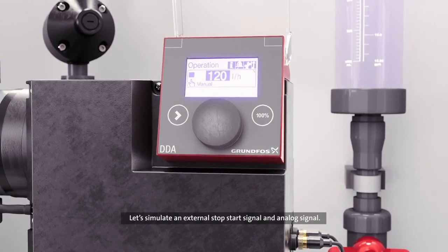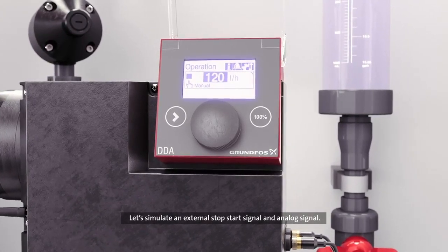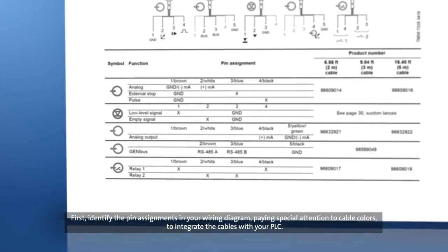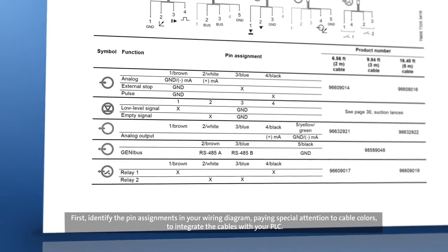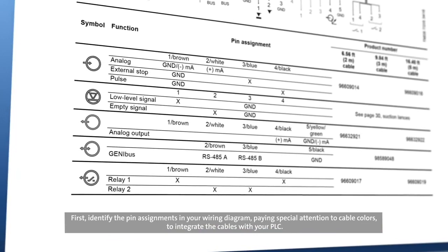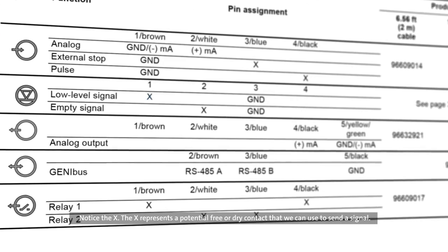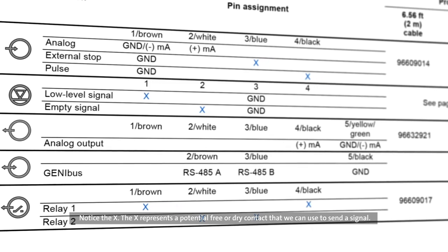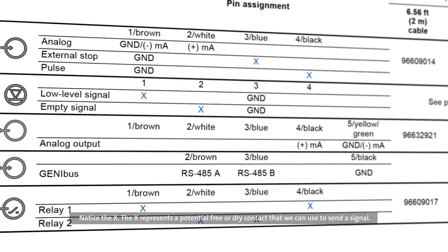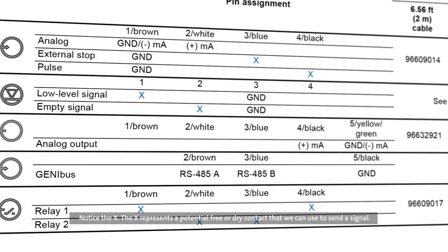Let's simulate an external stop start signal and analog signal. First, identify the pin assignments in your wiring diagram, paying special attention to cable colors to integrate the cables with your PLC. Notice the X. The X represents a potential free or dry contact that we can use to send a signal.